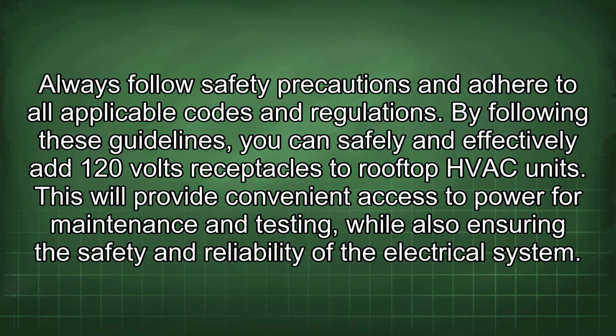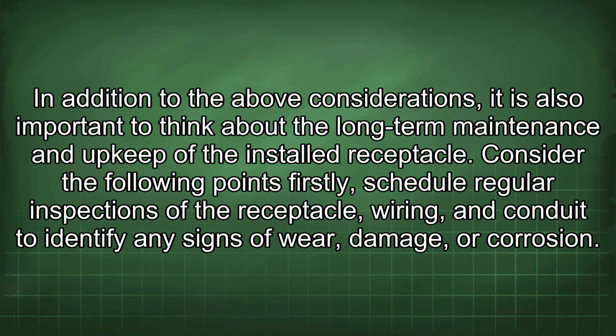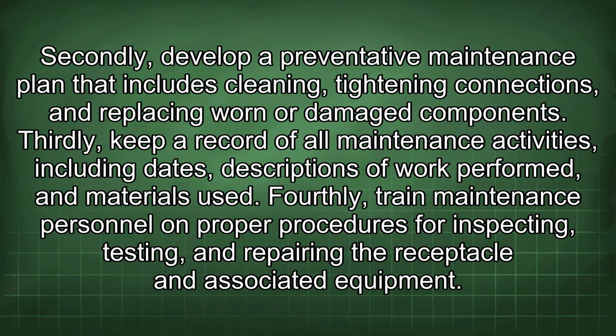This will provide convenient access to power for maintenance and testing, while also ensuring the safety and reliability of the electrical system. In addition to the above considerations, it is also important to think about the long-term maintenance and upkeep of the installed receptacle. Consider the following points. Firstly, schedule regular inspections of the receptacle, wiring, and conduit to identify any signs of wear, damage, or corrosion. Secondly, develop a preventative maintenance plan that includes cleaning, tightening connections, and replacing worn or damaged components.